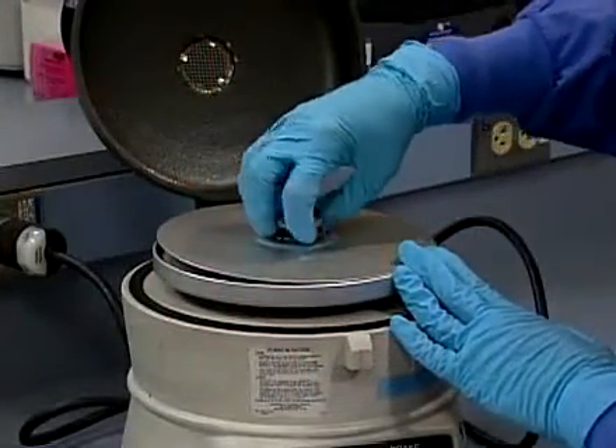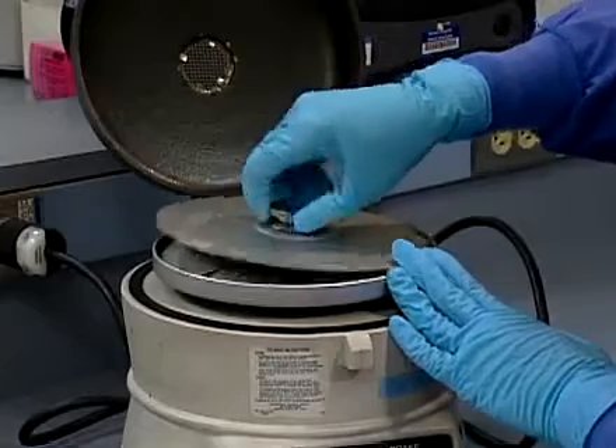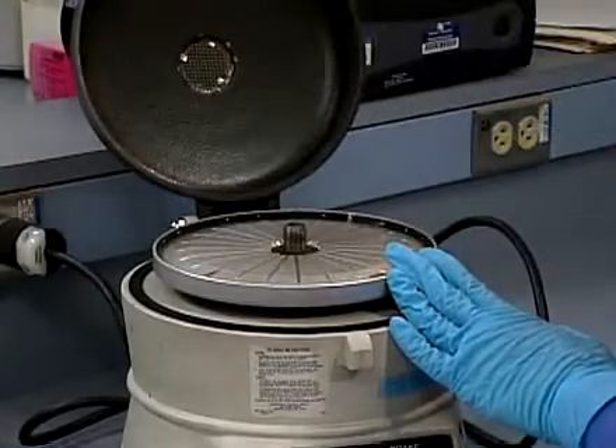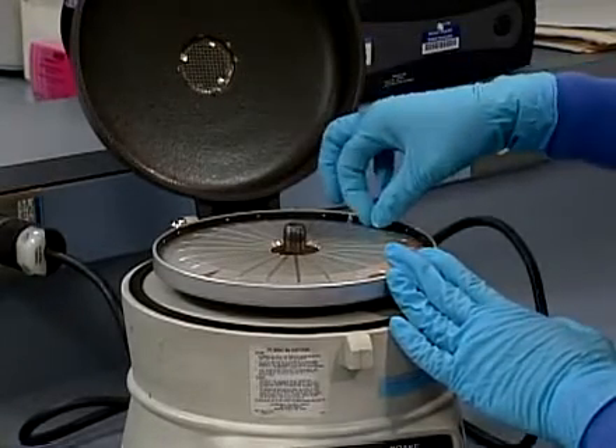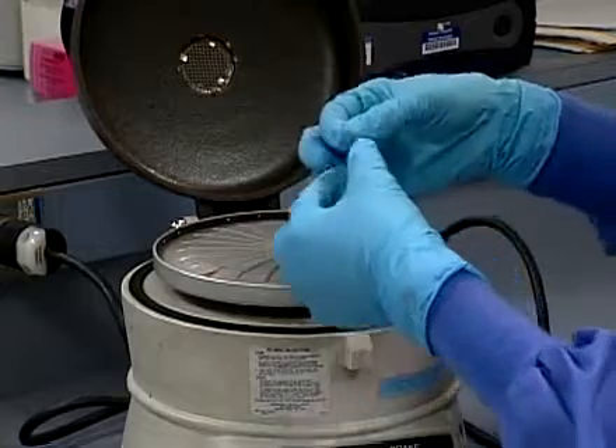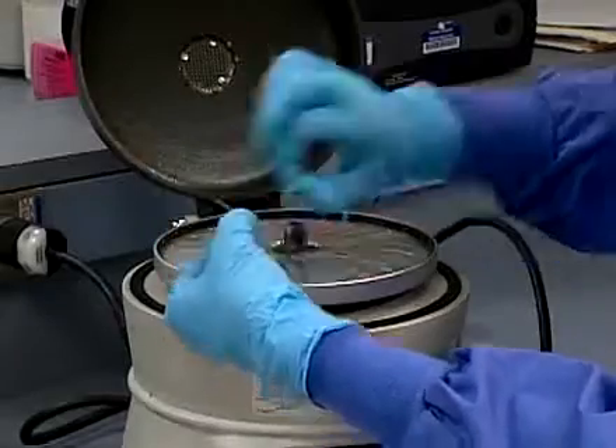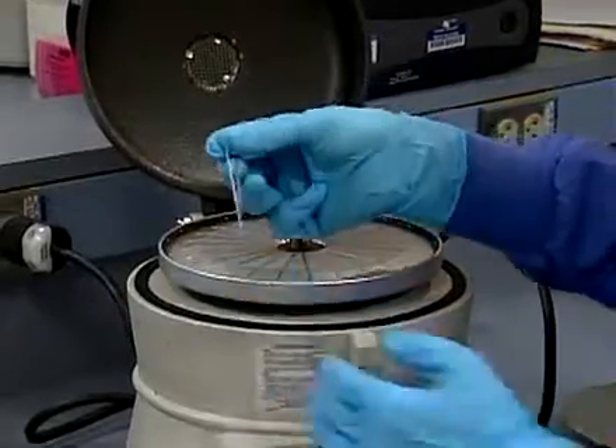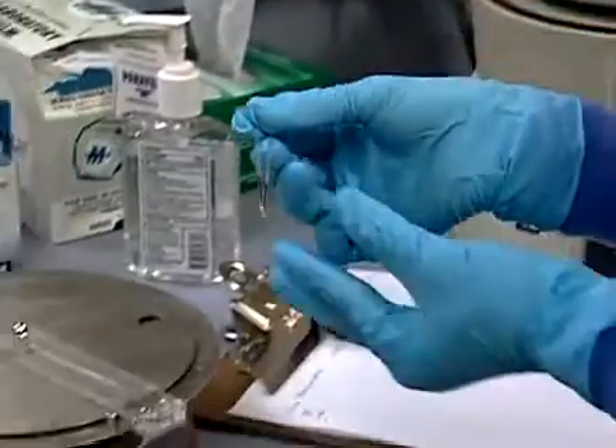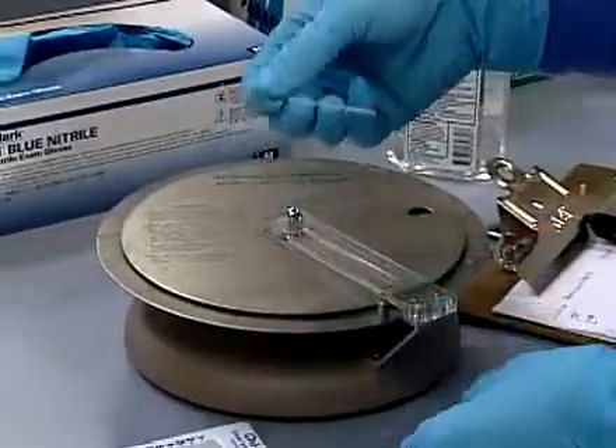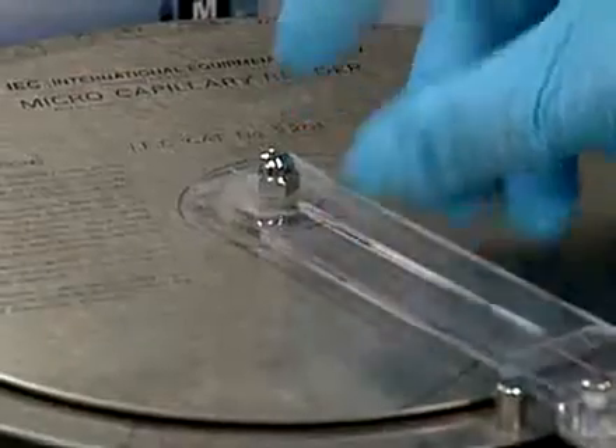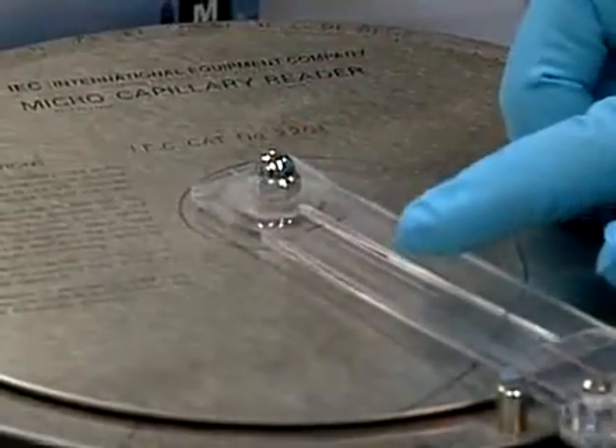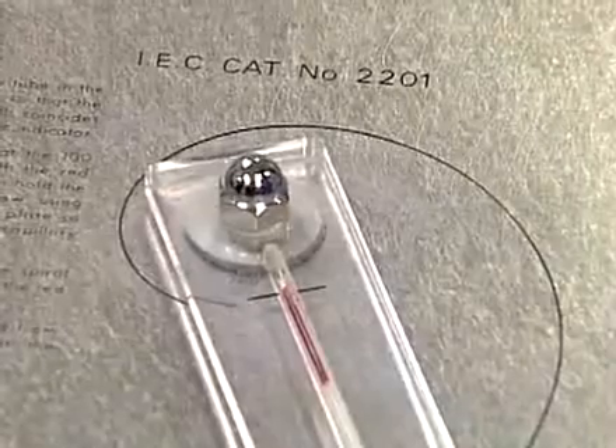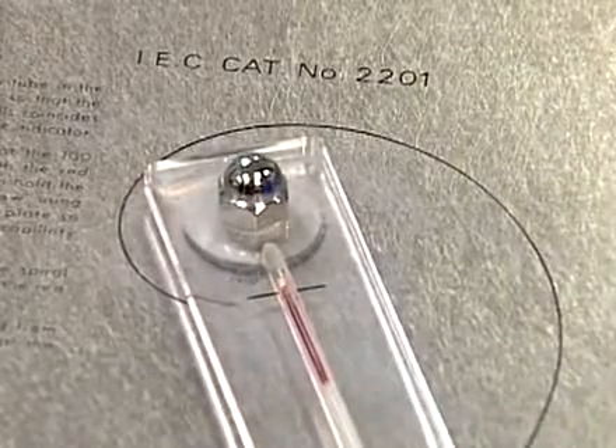If your centrifuge does not have a reading device, or if you used capillary tubes without a calibration line, or if you filled the tubes above or below the calibration line, you will need to use a hematocrit reader. Place the first tube in the hematocrit reader with the junction of the sealing compound and the red blood cell column at the 0 mark.